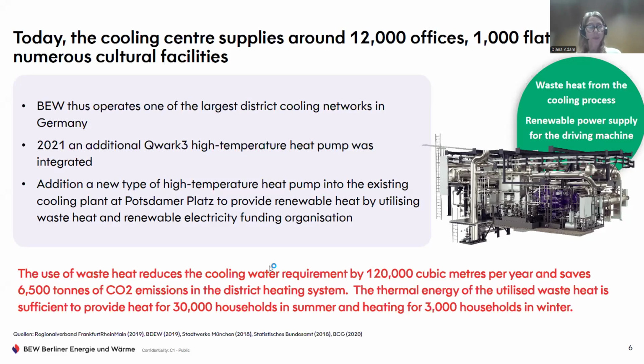This is a traditional cooling grid, but today there will be an opening for something new. We had chillers which in summer blow hot heat into the air, heating up a city already condensed with heat. So we installed a highly innovative project: a high temperature heat pump that uses the waste heat from the existing cooling grid and reuses it for heating. We collect this heat and feed it into our heating system, providing renewable heat through utilization of waste heat and renewable electricity.